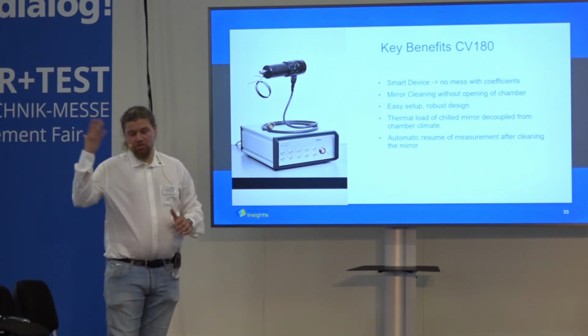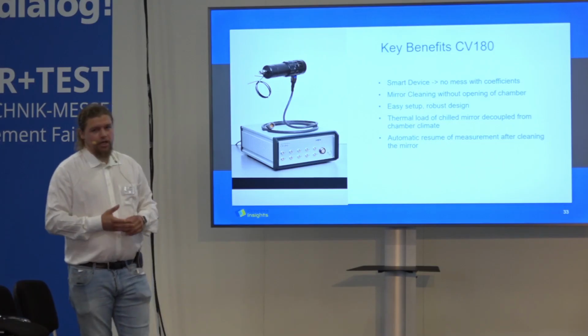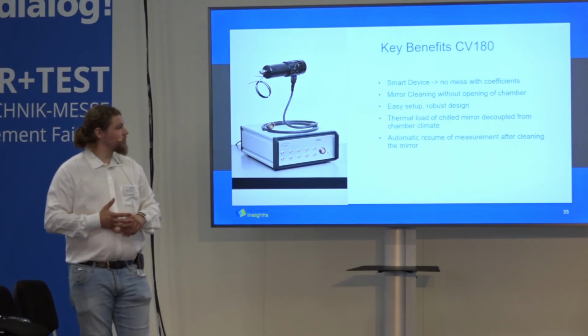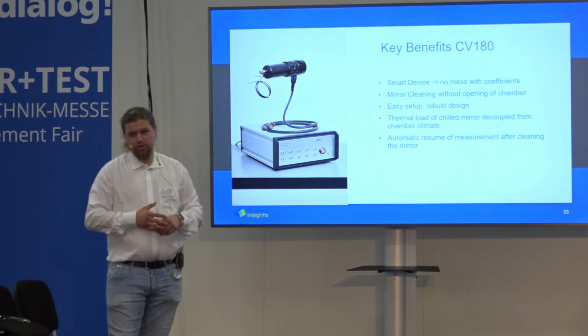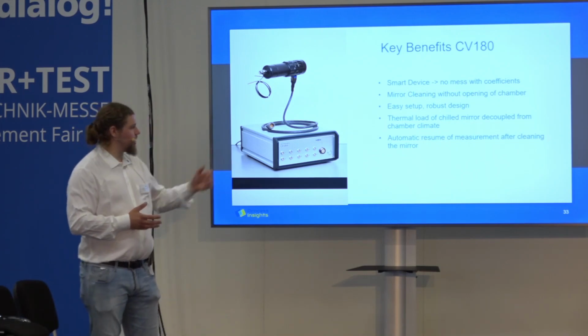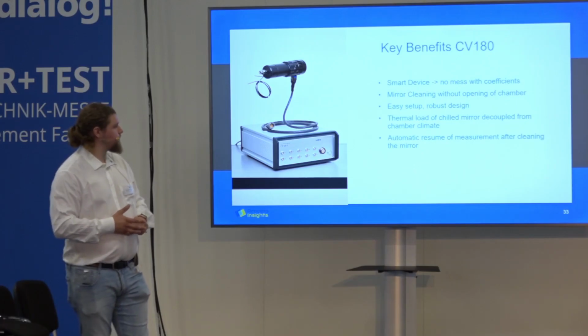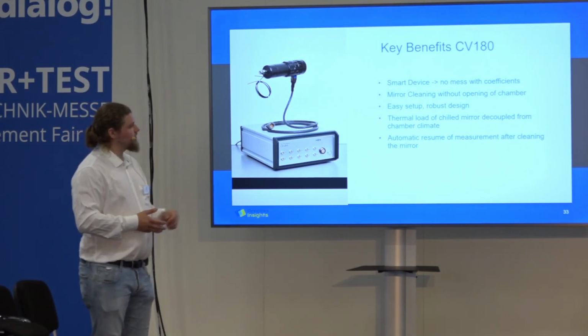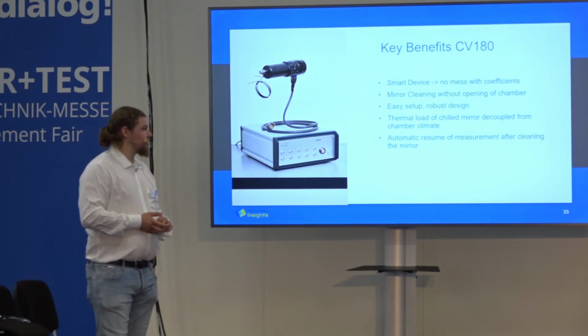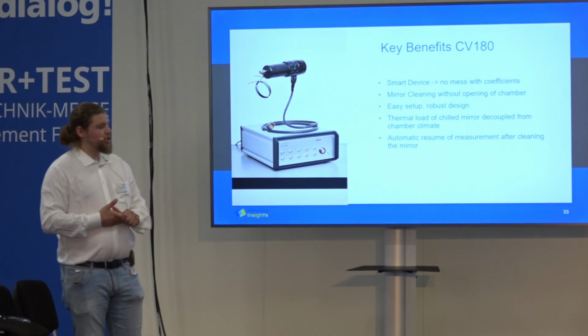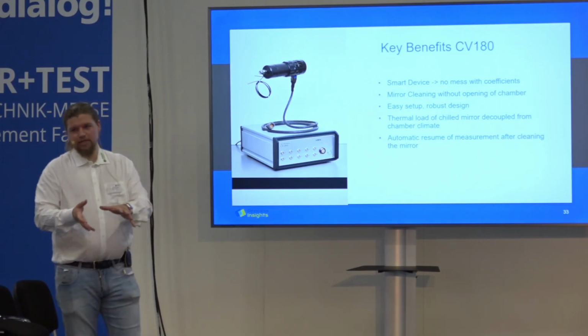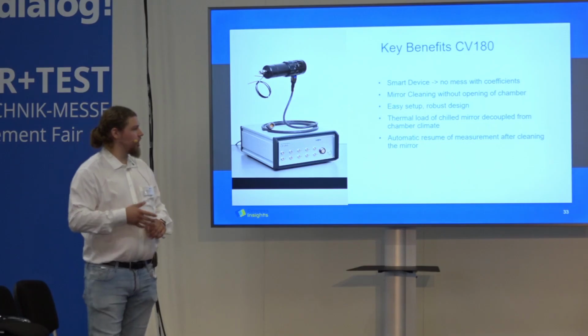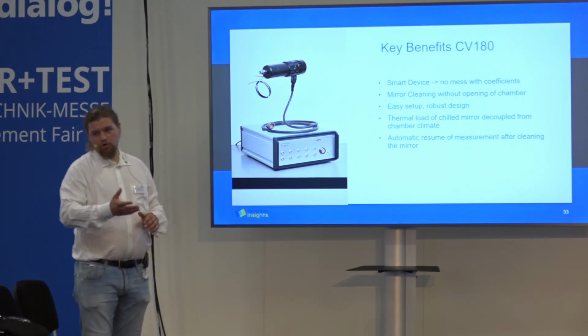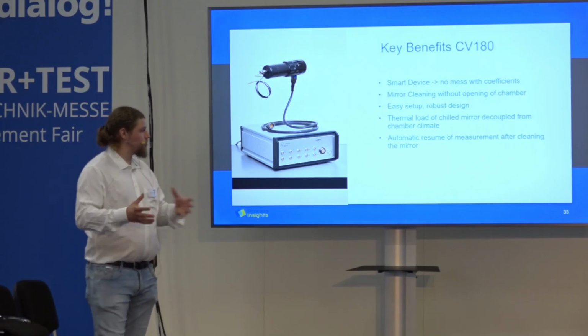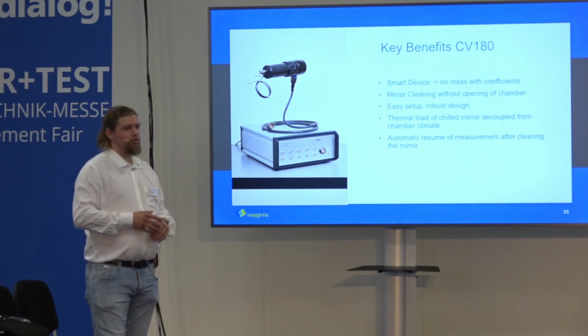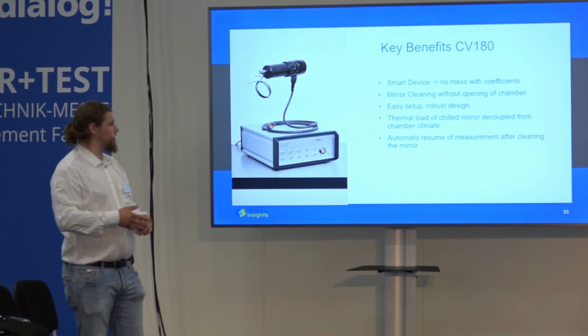This might, I'm just having the thought in the moment, if you have health risky substances which you have in the chamber, this could be a new opportunity and solution for that. But there are also others. You have an easy setup and robust design, and the thermal load of the chilled mirror is now, as said, not anymore inside the chamber but outside. So you have no thermal influences. The flow of the chamber is of a higher quality, representative also for the test scenario.